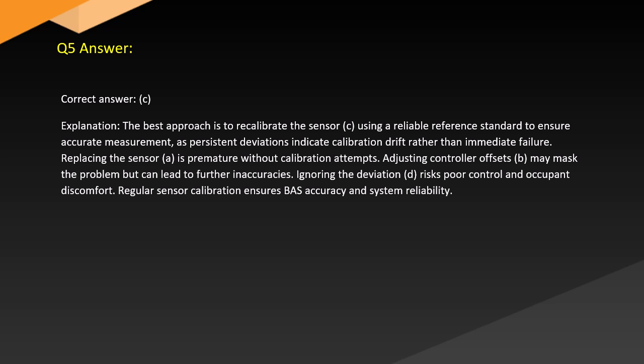Replacing the sensor, A, is premature without calibration attempts. Adjusting controller offsets, B, may mask the problem but can lead to further inaccuracies. Ignoring the deviation, D, risks poor control and discomfort. Regular sensor calibration ensures BAS accuracy and system reliability.